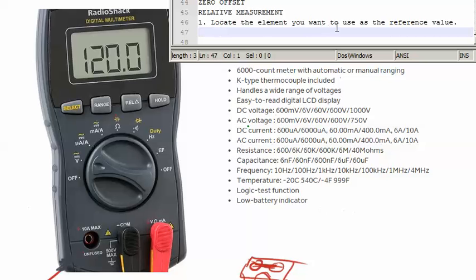So it says 1, locate the element you want to use as the reference value. Component or circuit, I don't know where I got element. Then select your function, say, ohms, and measure the reference value. Then when the reading appears, hit the rel delta. While rel delta is displayed, measure the other component or circuit. I guess hitting rel delta will set the view up here to 0, and when you measure another component, the meter will display the value relative to the reference value. Then, to exit the relative measurement, press that button again.